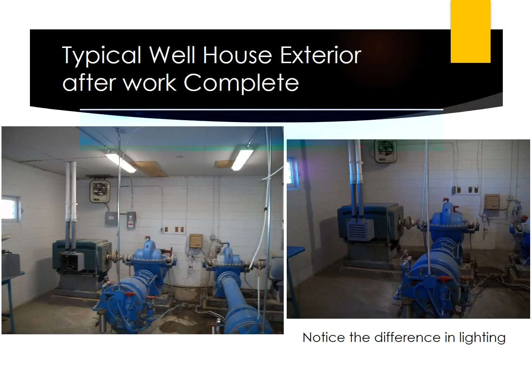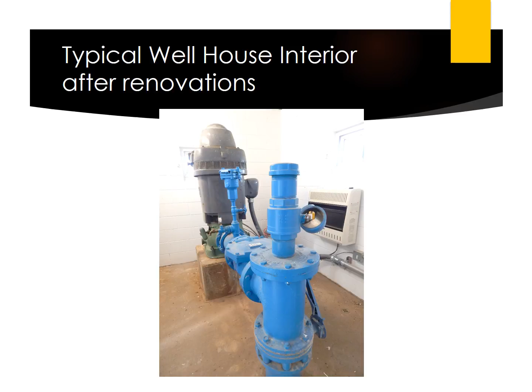Once the city could shut down a well for rehabilitation, the existing electrical equipment, piping, and wiring were removed and the new installation began. The new electrical equipment, control panel, variable frequency drive, line filter, and reactor, transformer, and lightning arrestor were prefabbed into a modular system for quick field installation.